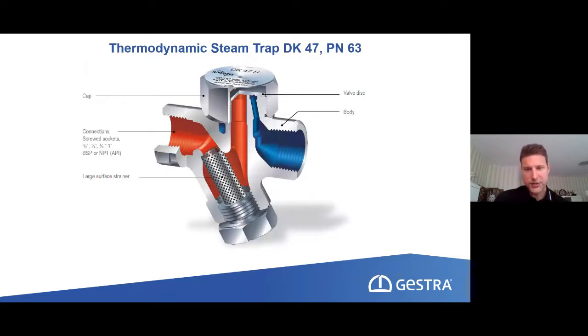So yes, let us speak about the thermodynamic type of steam trap, the so-called DK. And it works very simply, I would say. Here's the condensate inlet. It also travels through a strainer, and then all the magic comes from this valve disc. This valve disc has the size of maybe a little coin that you use for paying. And here's the outlet, and it works with the so-called Venturi effect.